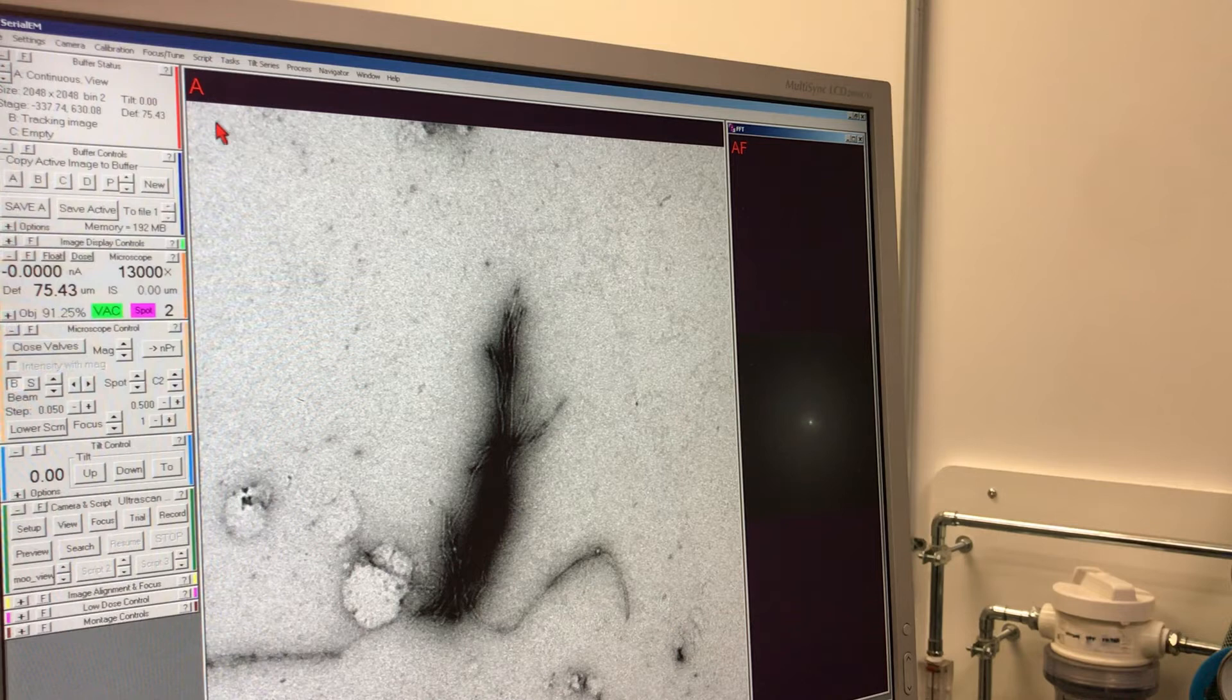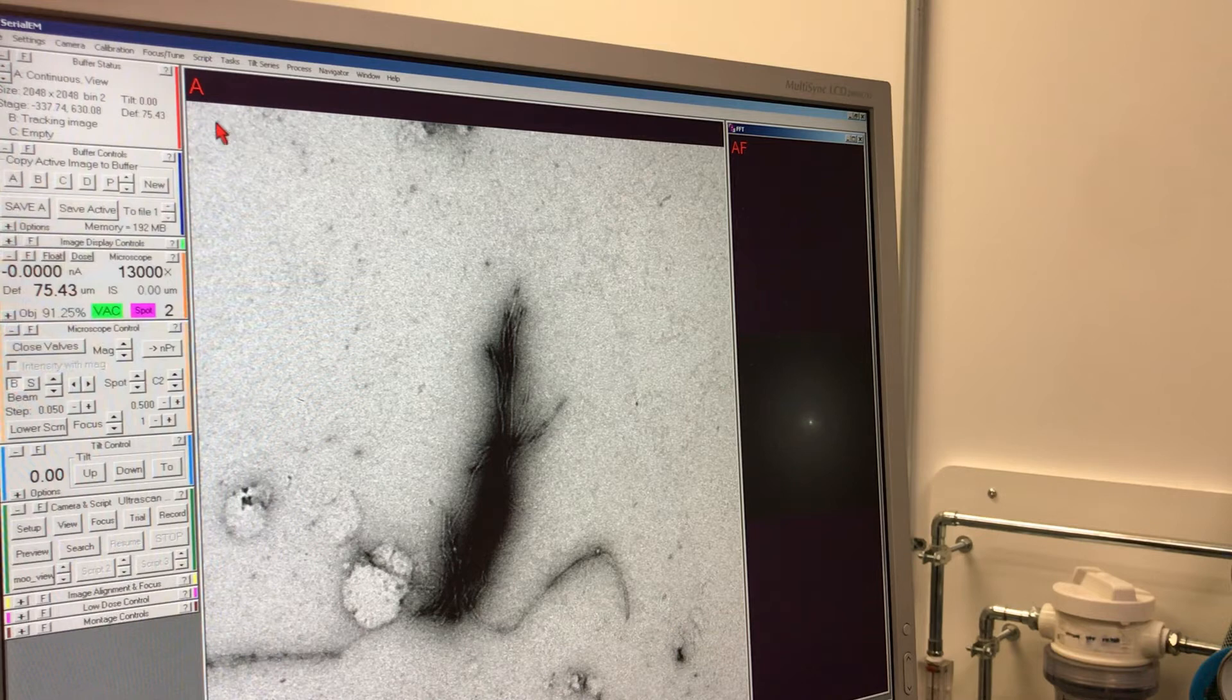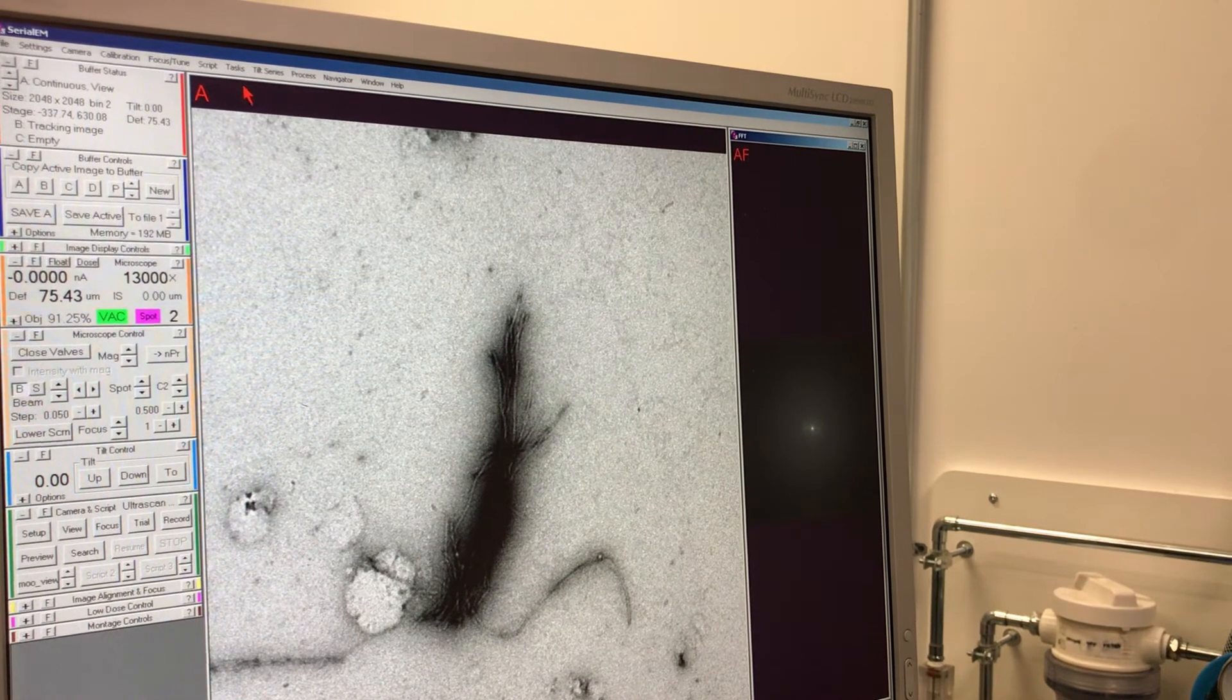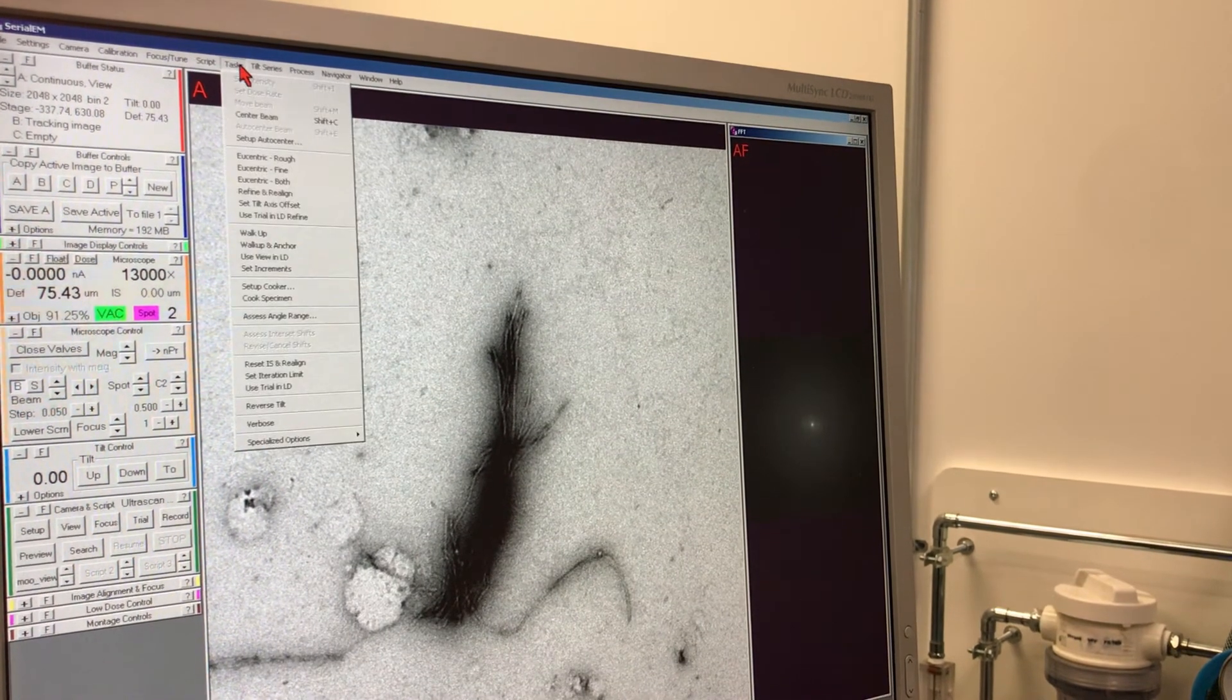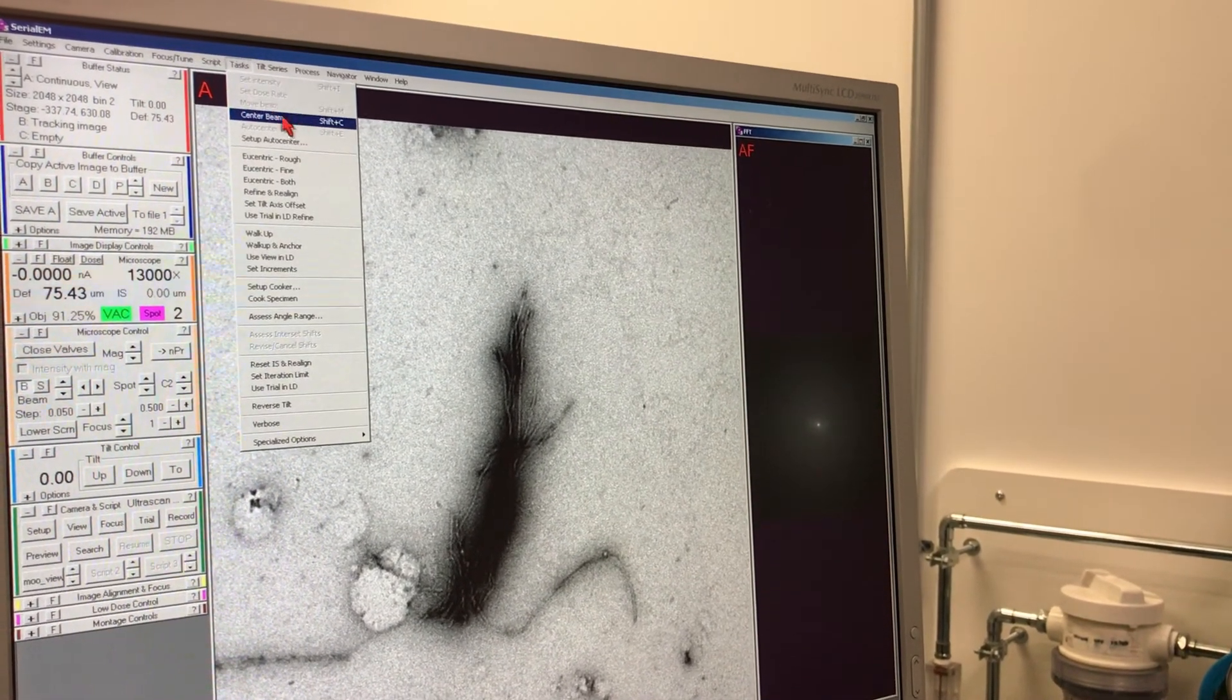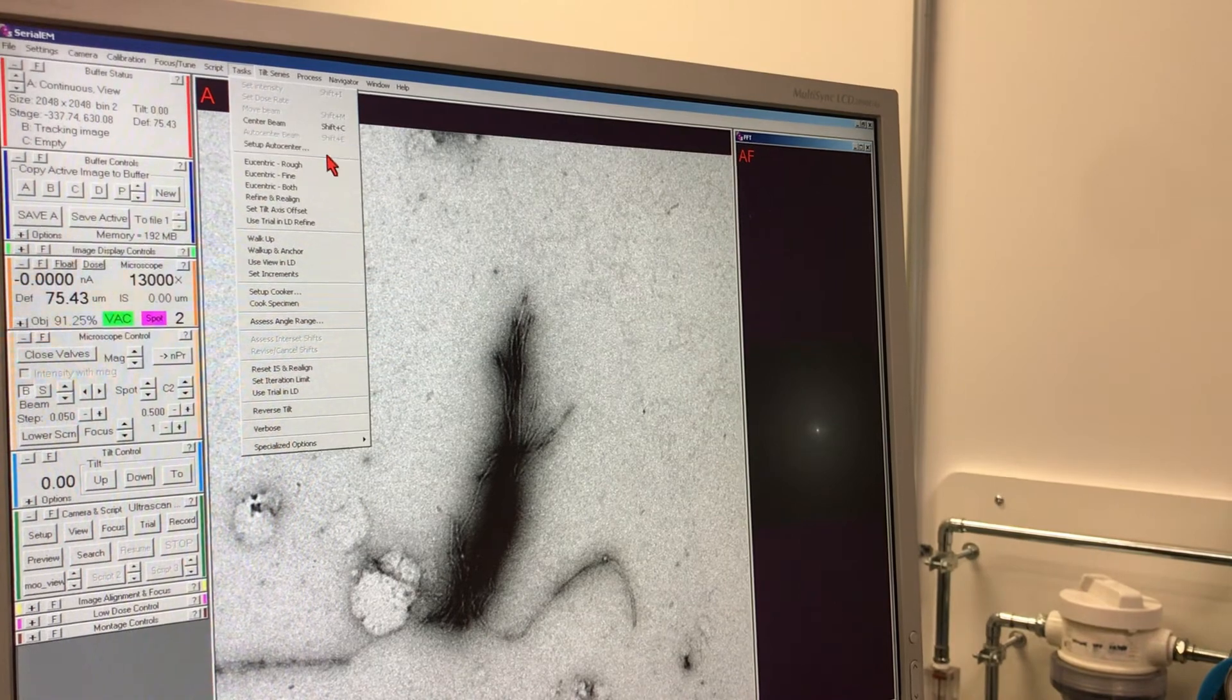One of the reasons why this image is blurry is because the sample, the specimen, is not in focus with the objective lens, meaning that you need to adjust the height of the specimen on the goniometer so that at whatever tilt angle you take an image, you should be able to find your object of interest in focus, giving you the right contrast or right features.